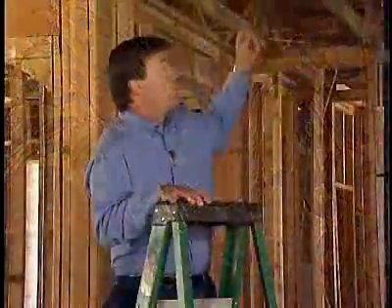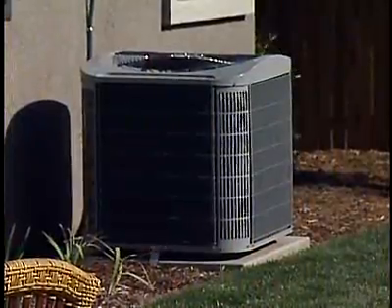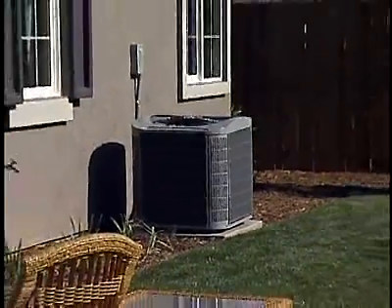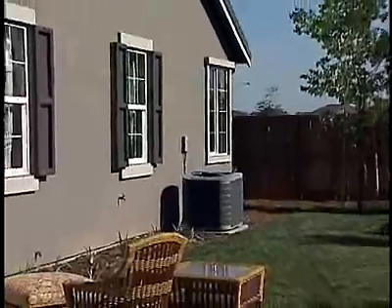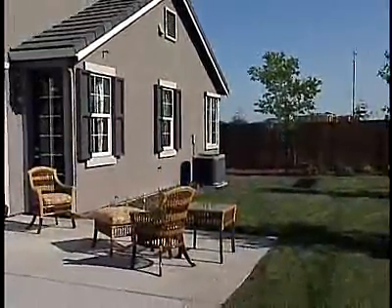Now, the way these systems typically work is that we have a thermostat which controls the system. When the house calls for heat or cooling, it sends a low voltage signal to this unit and it turns on the air conditioning system or the heating system. Now, the air conditioning system is made up of two components. We have an indoor coil, which we call the evaporative coil, which is in this device here, and then we also have an outdoor unit called a compressor. And basically what that compressor does, it rejects the heat from inside the home to the outside. So the outdoor coil tends to be a very warm coil, the indoor coil is cool, and that's how we get our air conditioning.